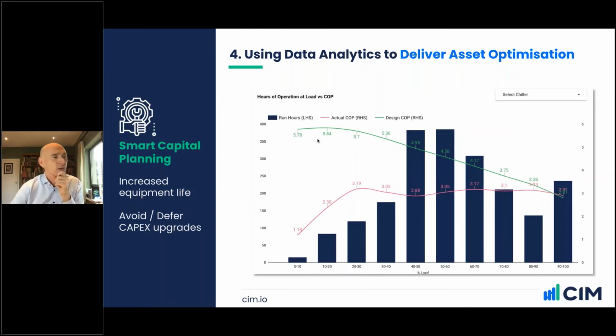And what we looked at was the design COP. So this is what they were sold when the chiller vendor came on day one to say that the COP of the chiller should be 5.8 at 10% load, and it should degrade to 2.8 when it's fully loaded. But what we did is we got empirical data to show the client that what they were actually running at was 1.8 at low load. The chiller was basically grossly oversized for what the load in the field was. It began to improve at maybe 20–30%, but it never got above a COP of 3.2.